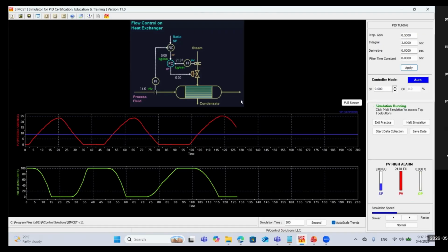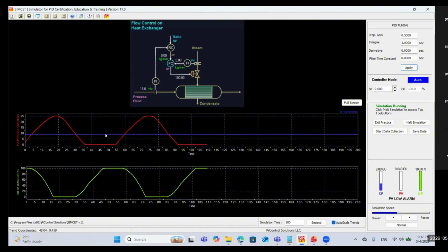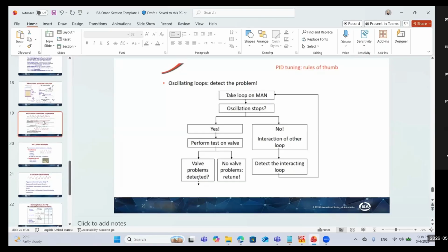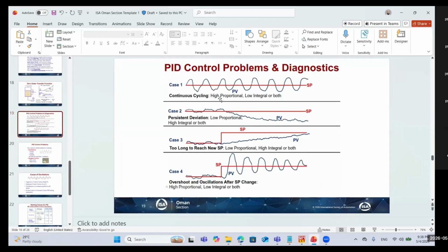So you can see, though proportional gain is low, again it's oscillating. Oscillations change the behavior of the oscillations. It's not the same as before, but it's still oscillating. That means it's because of proportional and integral, both, as mentioned in the slide. You can see here, continuous cycling, high proportional, low integral, or both.